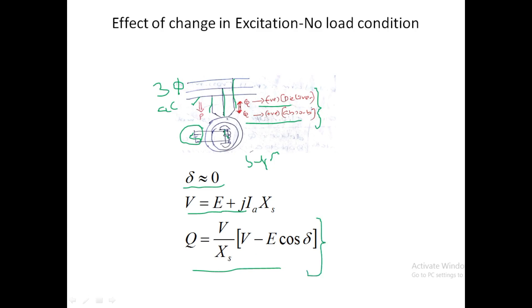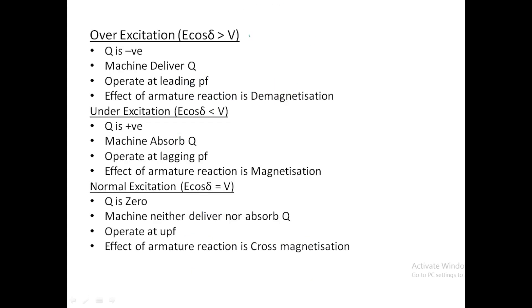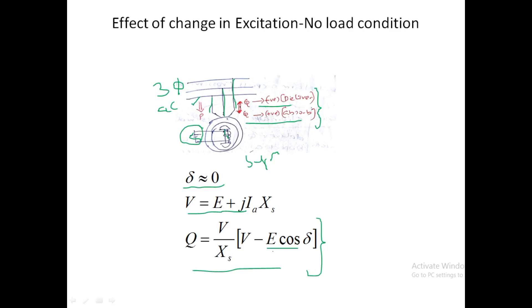We can consider three conditions. The first case is over-excitation, which means the term E cos delta will be greater than V. We are giving more DC supply to the field coils than the rated value. If E cos delta is greater than V, then Q will be negative.